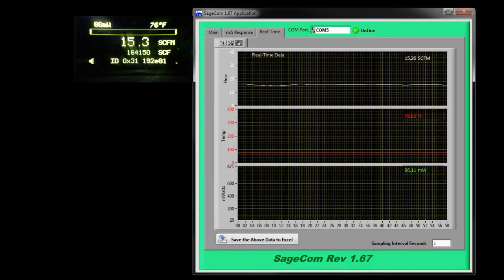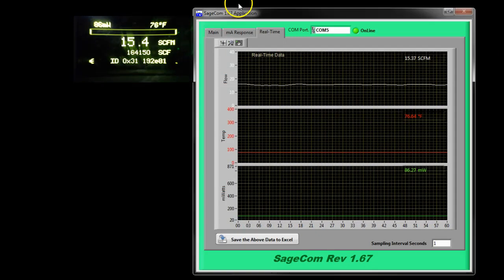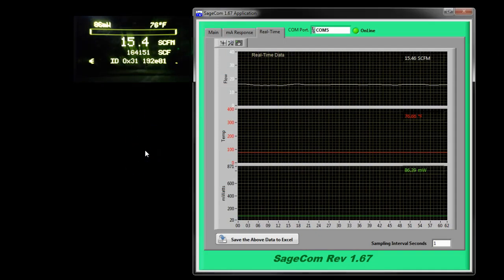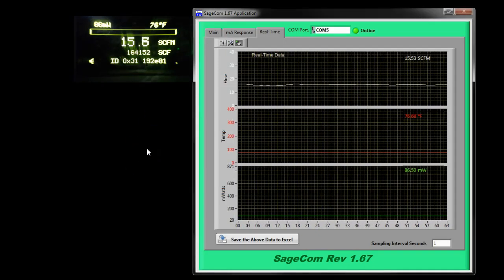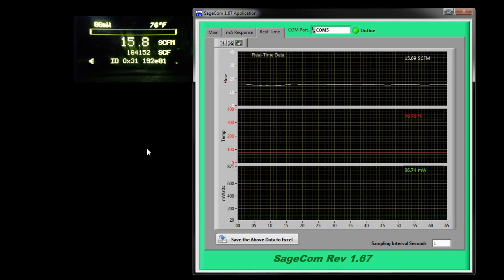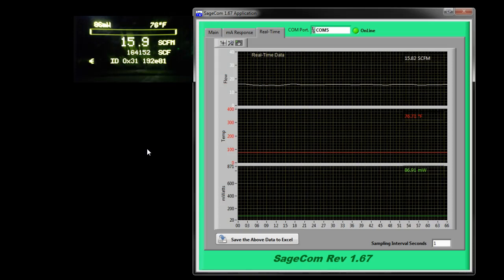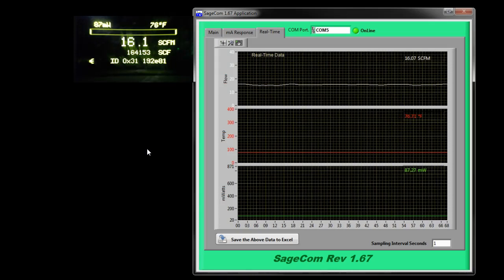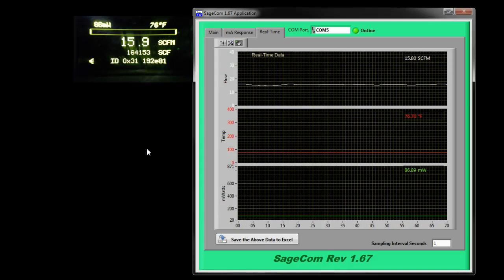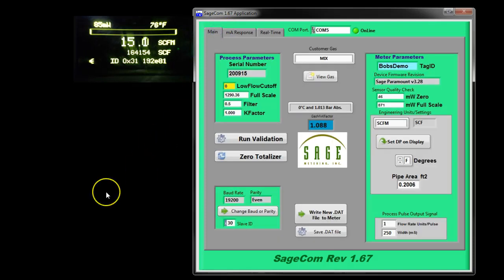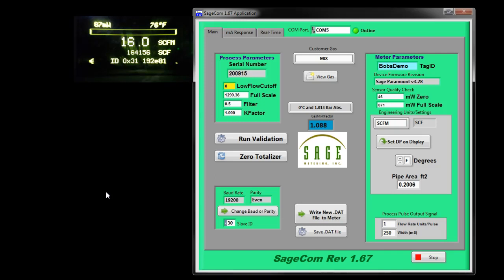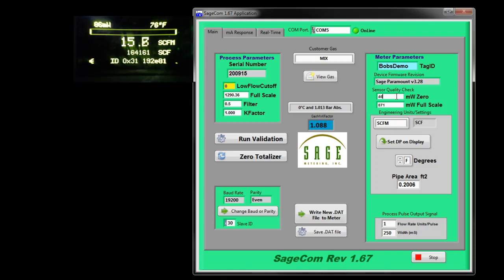Sorry about that pop-up on my screen. I also want to do the most important thing for customers who have QC programs or visitors from their ISO inspector or whomever and that is validation. It also verifies your meter hasn't drifted, shifted, or changed since the last NIST traceable calibration. Now, let's take a moment and look at what the setting was at the factory. As you know, our zeroing chamber is used to take a zero, a no-flow reading, with your gas at your pressure and that value is stamped on the outside of the meter and is also on your certificate of calibration as well as on the software program. So, that number is going to be looked at when we do the in situ.